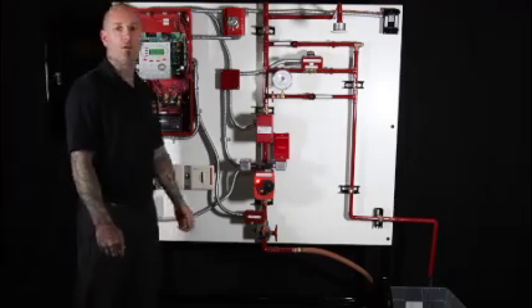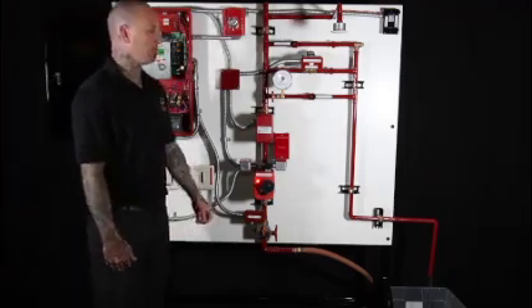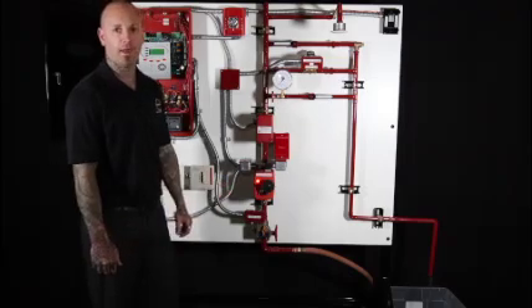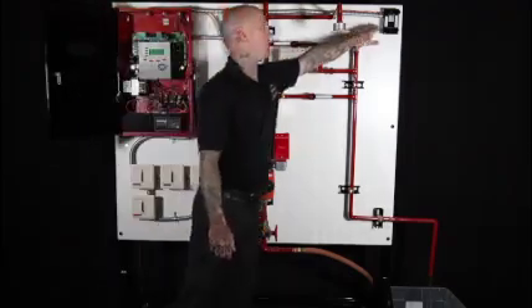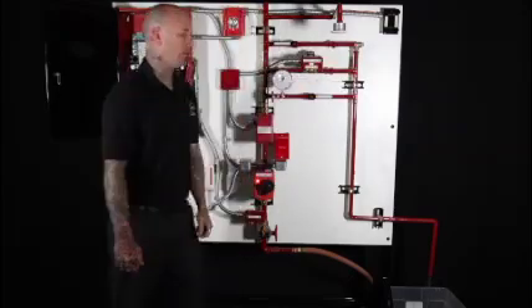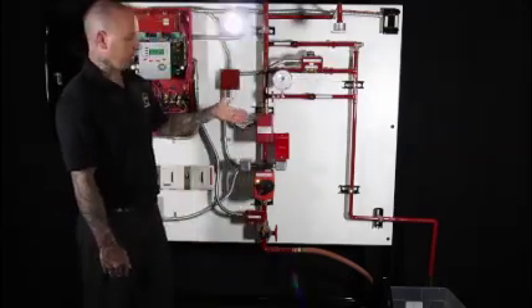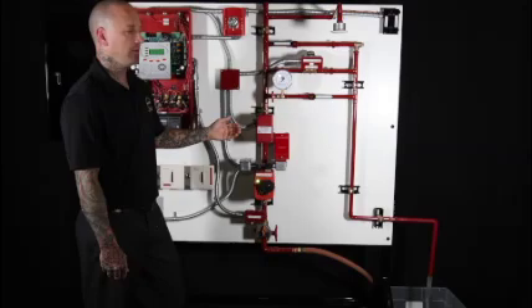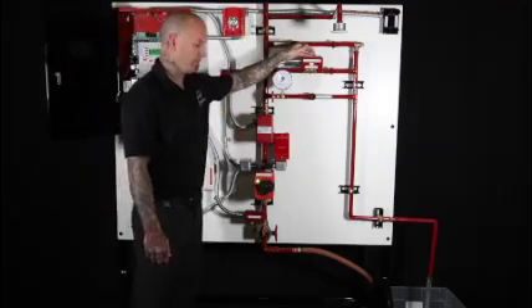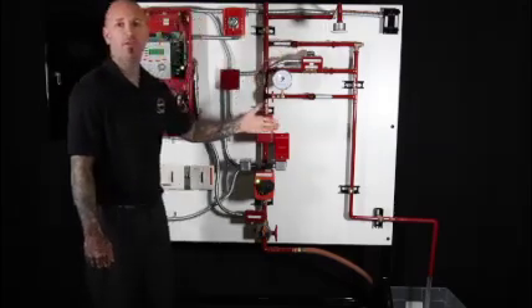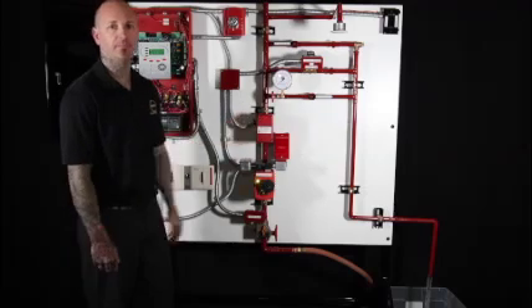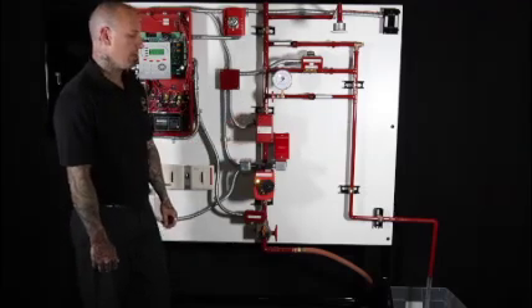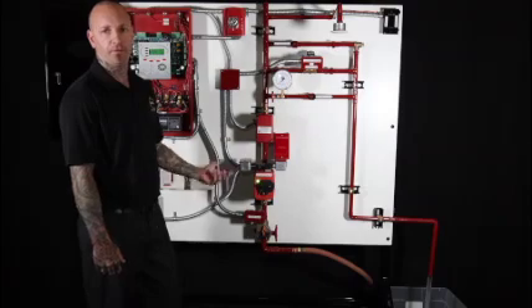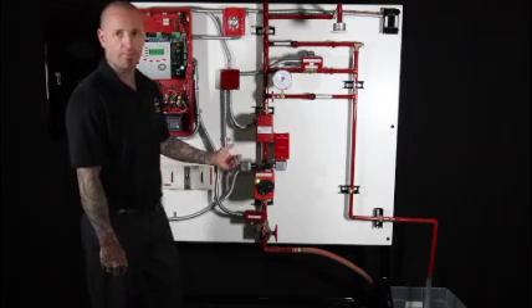So I'll silence that alarm at this time. But say we have a fire after this happens. Sprinkler head goes off. System turns itself back on, shuts the drain off, and continues to fight the fire as designed. At this time, I'll have to shut the water off manually.